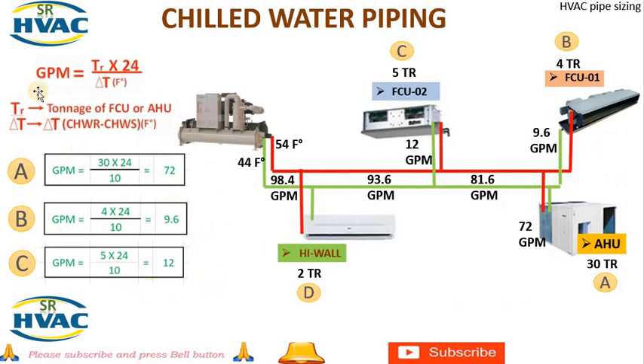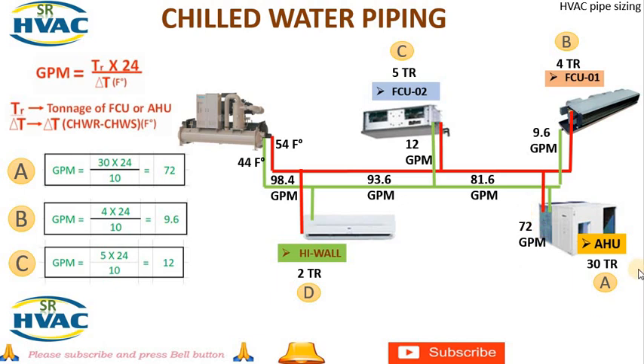We need to know the GPM for these pieces of equipment. For the calculation of GPM for the AHU and FCUs, we use the formula: GPM = (Tons of Refrigeration × 24) ÷ ΔT, where ΔT is the difference in temperature between the chilled water return and chilled water supply in degrees Fahrenheit. Since we know the capacity of the FCUs, high-wall unit, and AHU in tons of refrigeration, we will apply these values in this formula to calculate GPM.